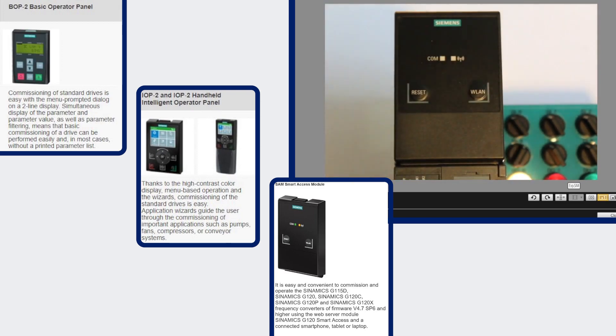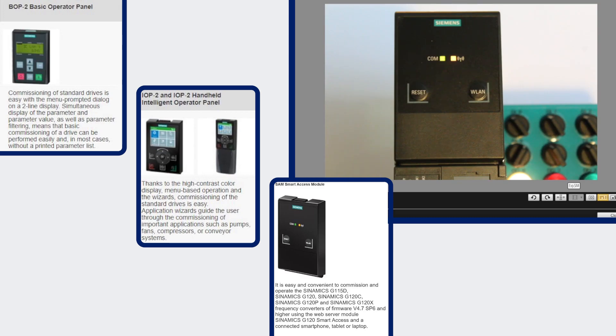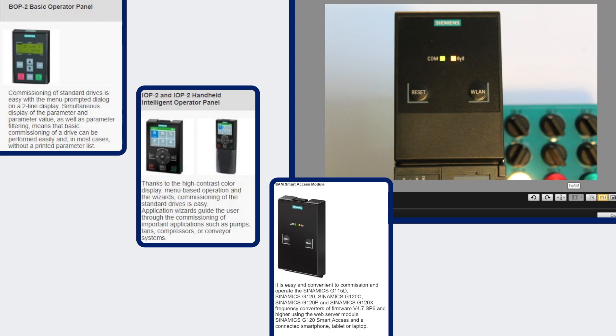The smart access module is intended for commission and troubleshooting but not a permanent operator panel. It's a wireless web server module or access point, so you can use any type of wireless device such as Android, Apple, PC, or laptop to access through Wi-Fi wirelessly the web pages via the built-in web server.